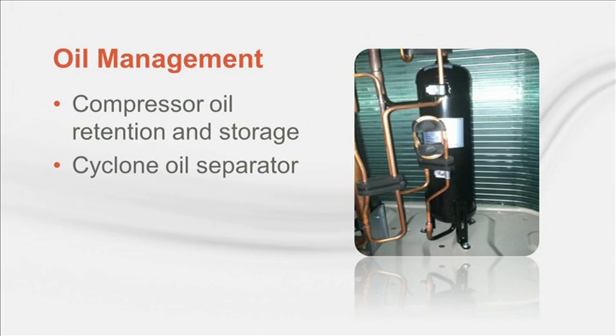Yet since the separator isn't 100% effective, some oil will still circulate out in the system. So VRF systems have a built-in oil recovery cycle, a flush cycle if you will, which is initiated based on compressor runtime, frequency, and other factors. When the oil recovery cycle begins, an expansion valve will open to a minimum setting and the compressor will speed up to flush the oil back to the compressor in the outdoor unit.